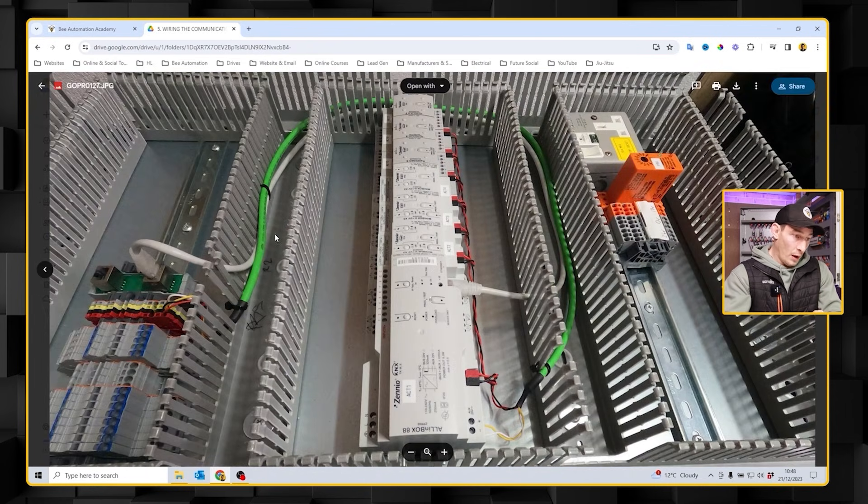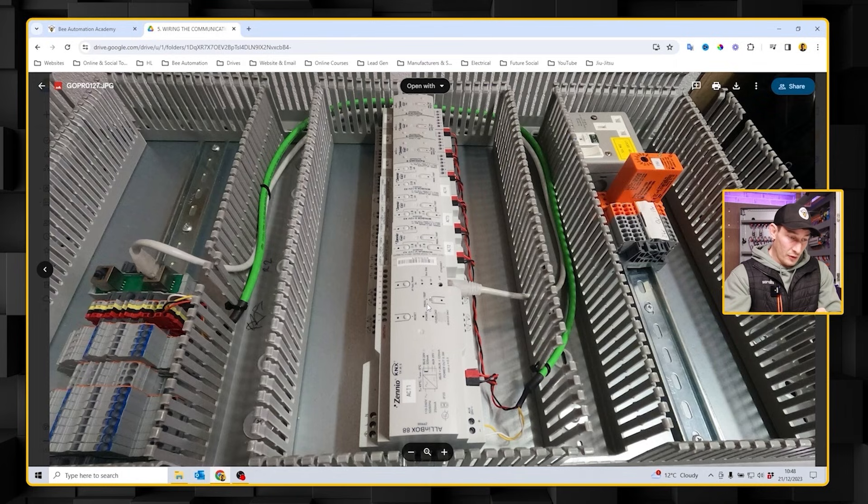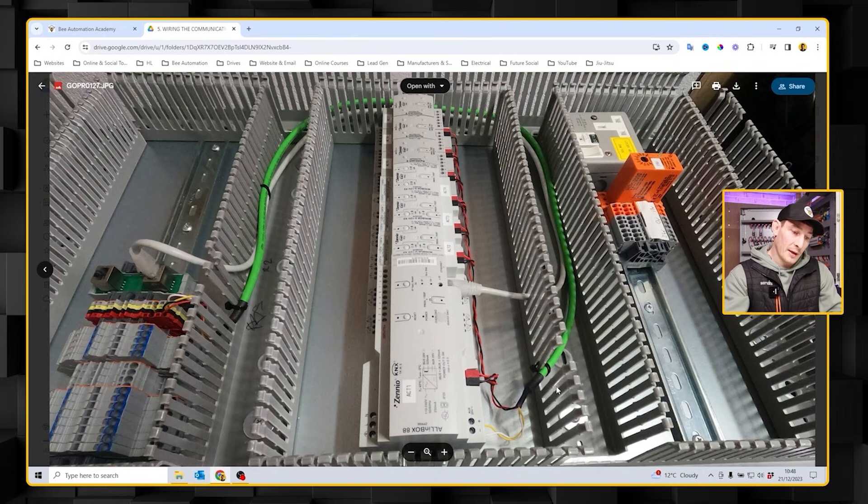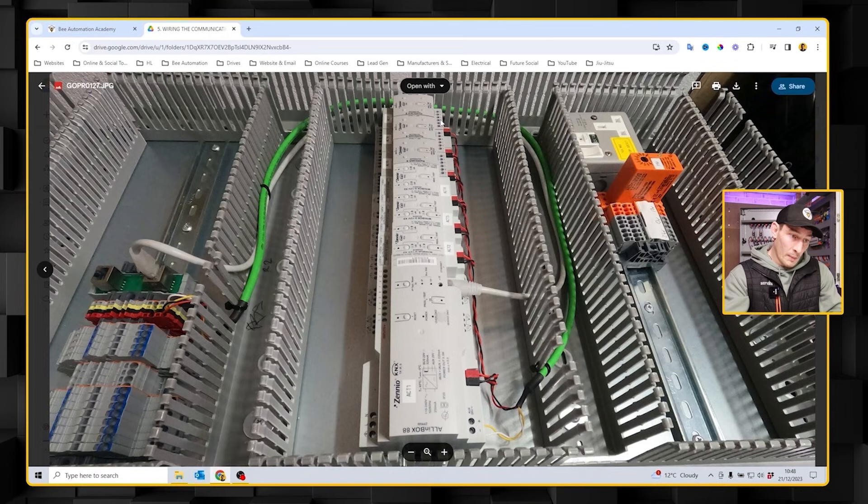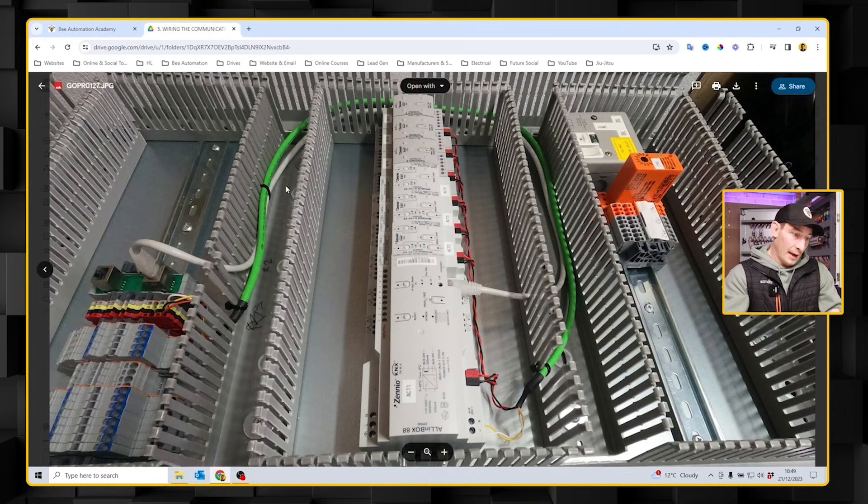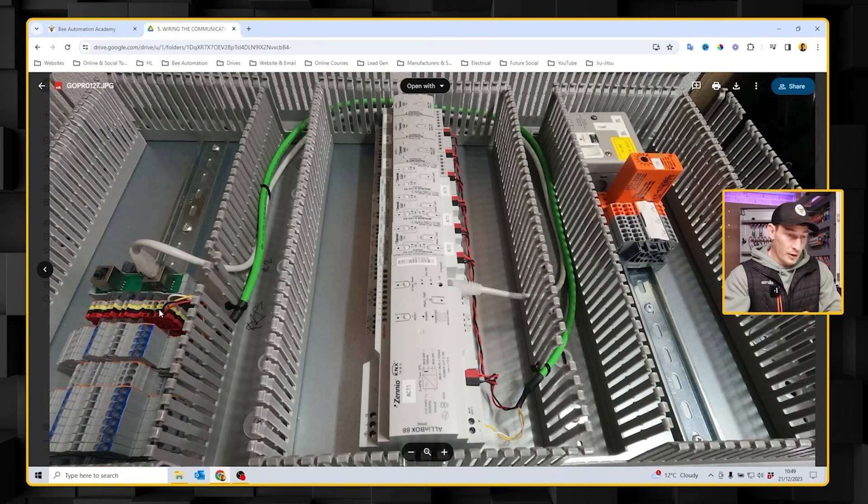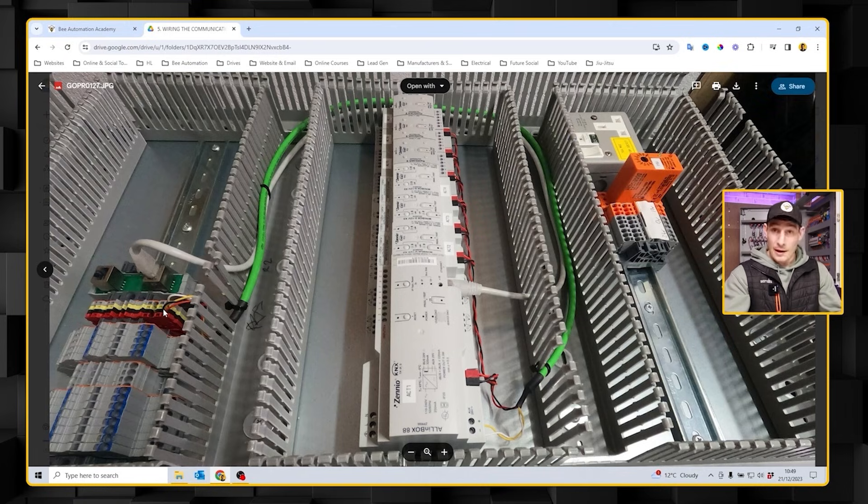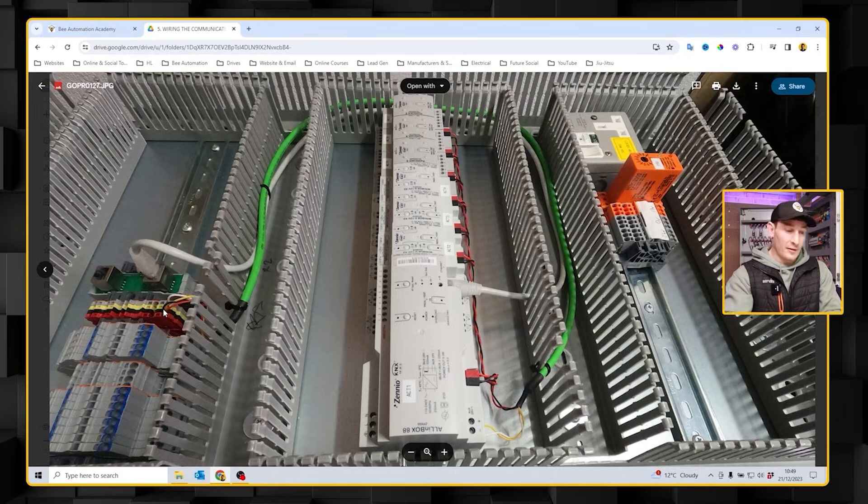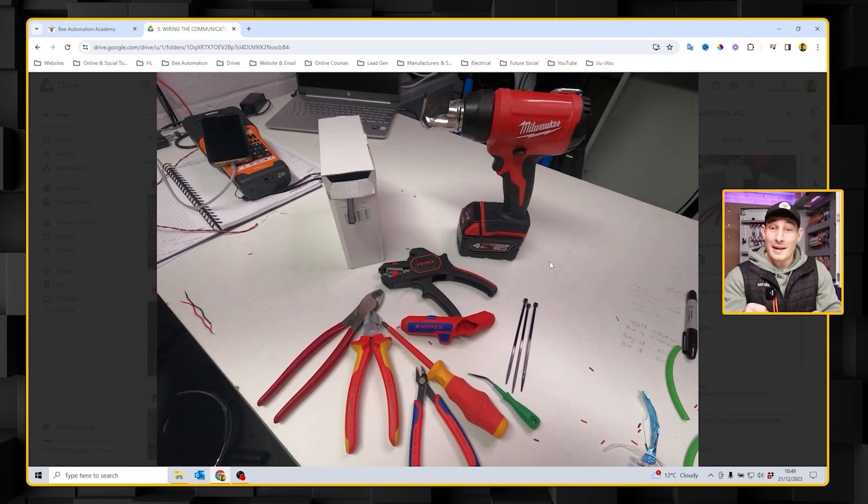So Ethernet in white going out from the main controller to the terminal blocks then meeting the incoming cable, and same thing with the KNX cable - we're busing from the furthest module all the way to the main controller module and then out to the terminal blocks to have a KNX cable coming into the panel that feeds other devices in the field.